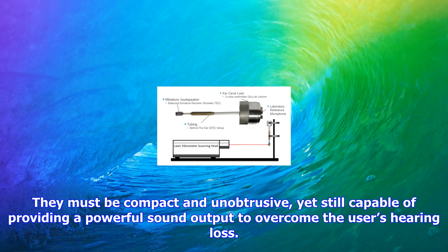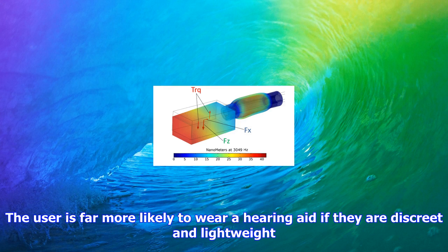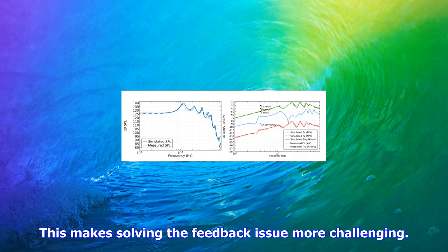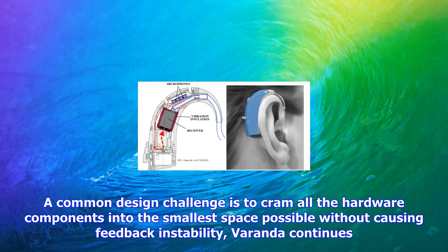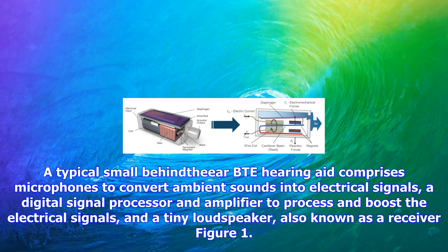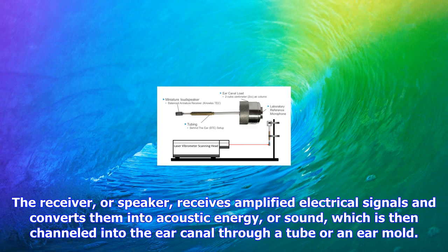When designing hearing aids, two major conflicting requirements must be accounted for by engineers. They must be compact and unobtrusive, yet still capable of providing a powerful sound output to overcome the user's hearing loss. The user is far more likely to wear a hearing aid if it is discreet and lightweight. This makes solving the feedback issue more challenging. A common design challenge is to cram all the hardware components into the smallest space possible without causing feedback instability, Veranda continues.